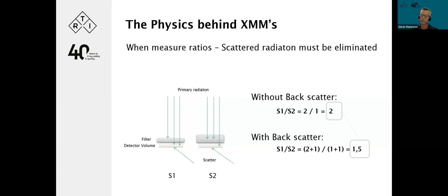And this is a characteristic that is needed for XMMs. From the other side, when measuring dose, you may want to have scatter. Depending on what dose parameter you want to measure, the backscatter should be there or shouldn't be there. If you want to measure incident air kerma, for example, then you don't want to include the backscatter. And that is pretty much what any XMM will measure because of its construction. But if you want to measure entrance surface air kerma, that includes backscatter, then one has to compensate for that or find other methods. And in a clinical situation, the backscatter can be enormous.